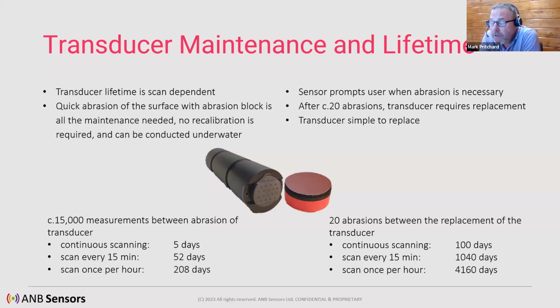So Nathan mentioned that we have a health status that's shown to the operator. It's outputted via our protocol on the sensor status and also the transducer status. So it will tell the operator when it requires abrading. It will also tell the operator when it requires replacing. Now, we say after 20 abrades, the transducer then requires replacing. So if you're doing that once every hour, that's over 10 years between replacements of the transducer. So it's a massive time if you're measuring at once per hour, 4,160 days. If you're doing continuous scanning, it's every 100 days.